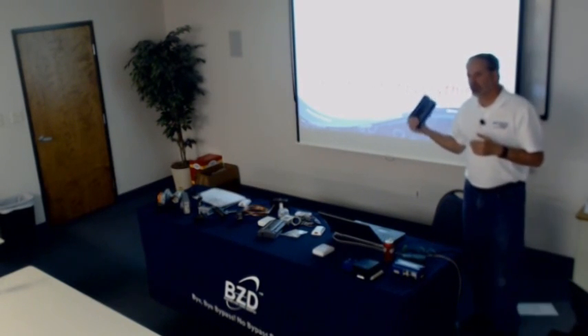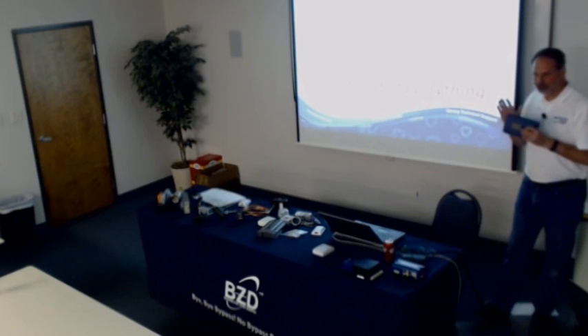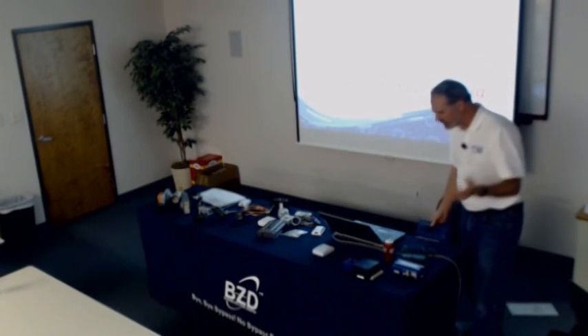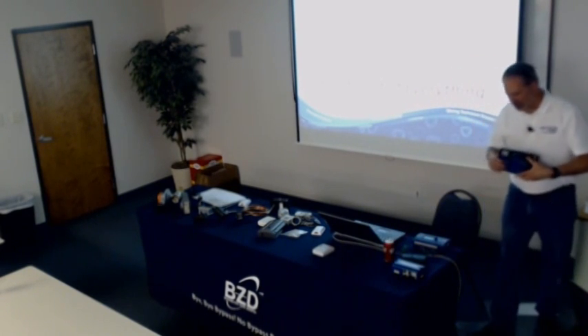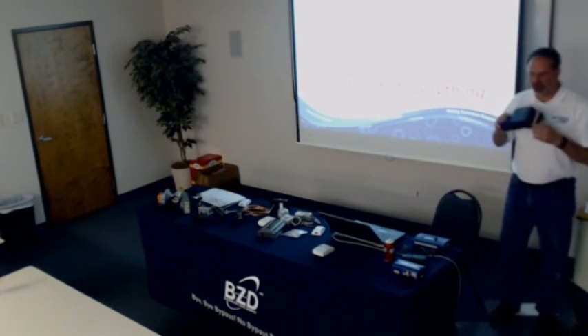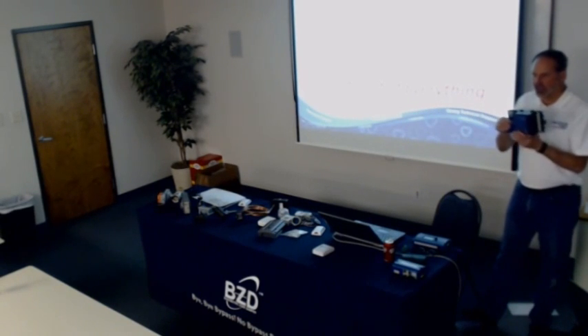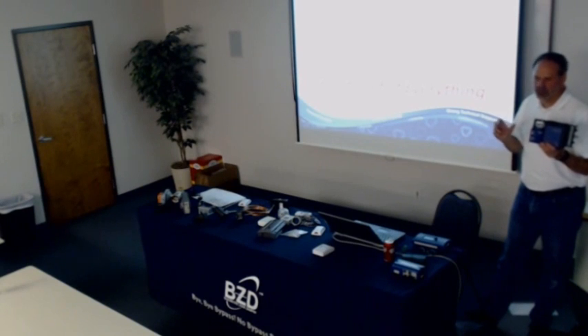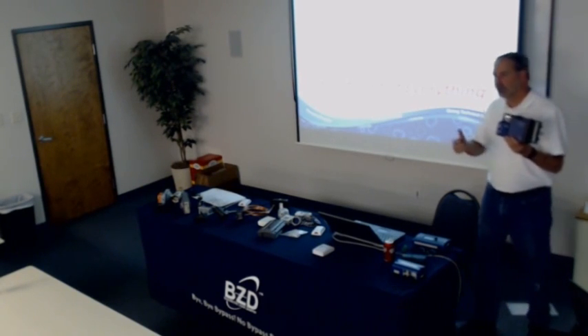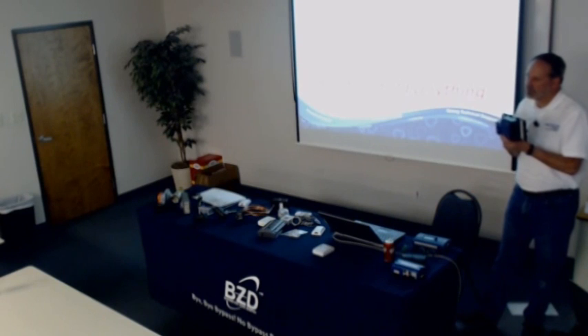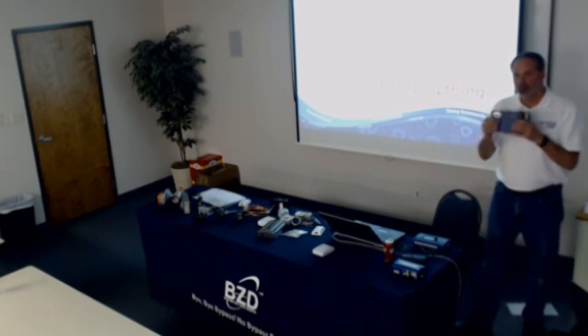And the new generation of Distech controllers, not only are they BACnet over IP, they're also their own little Wi-Fi hotspot. So when you have a VAV box, the new generation of VAV box, which is out today, we haven't embraced it yet. But if you want to wire it BACnet, just the same way you'd wire this one, BACnet or LON, you just plug in a little Wi-Fi device, and it has its own built-in graphic right in it. So using your cell phone, you can walk underneath that device. If you know the IP address of that device, it generates a graphic of this device and all the setup parameters right over your phone.